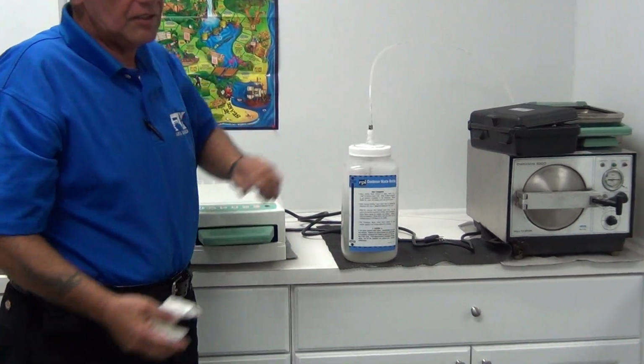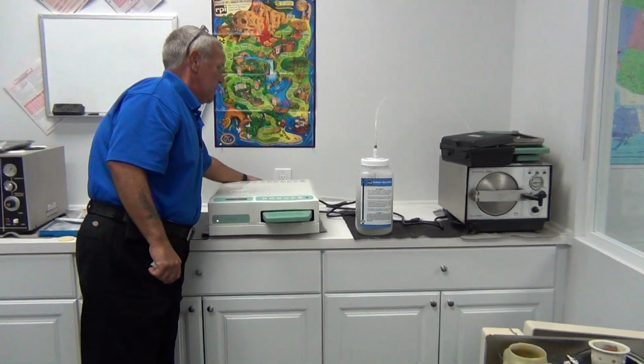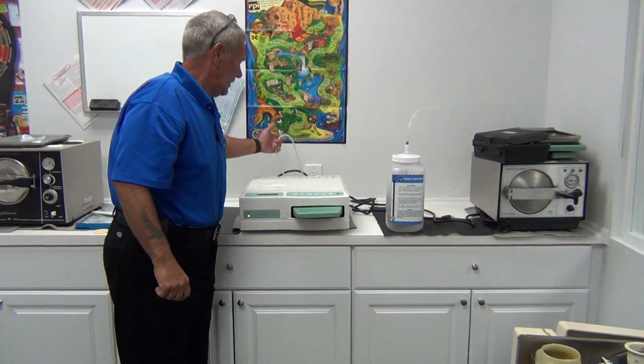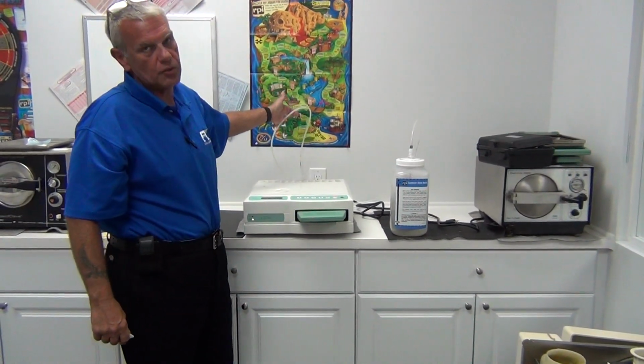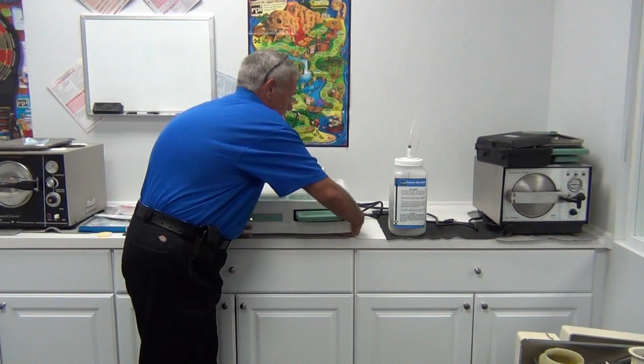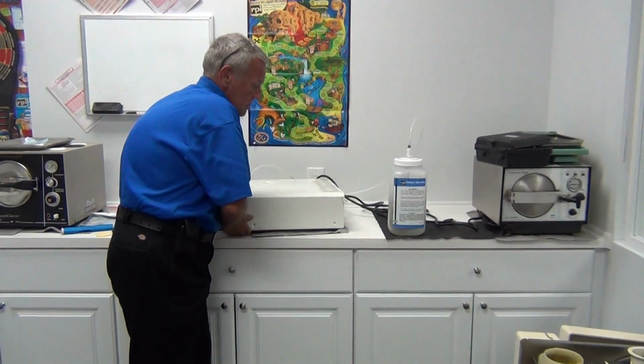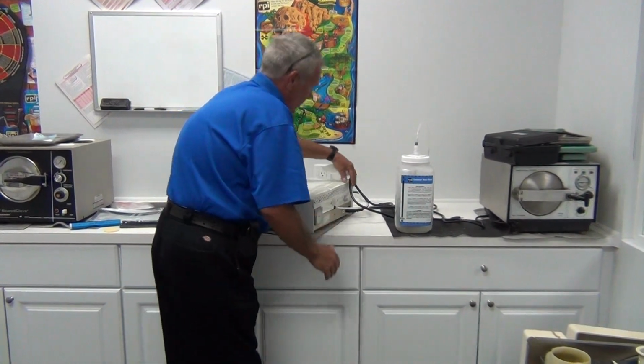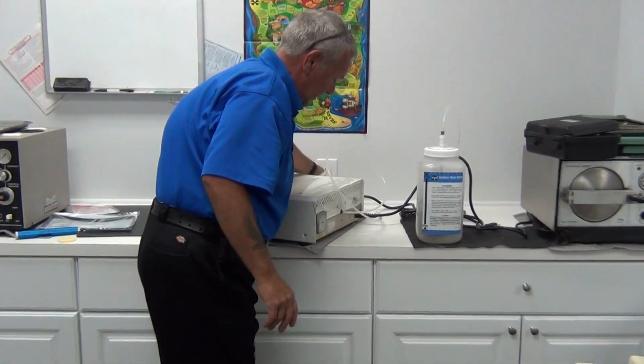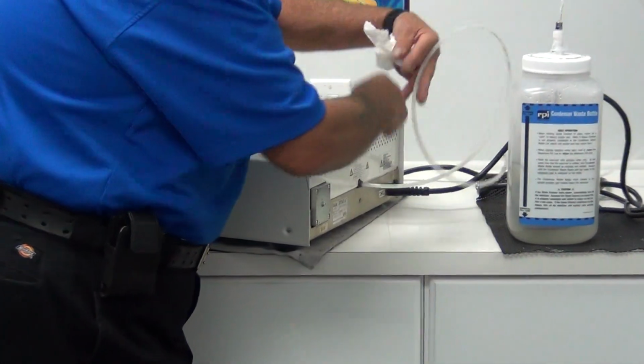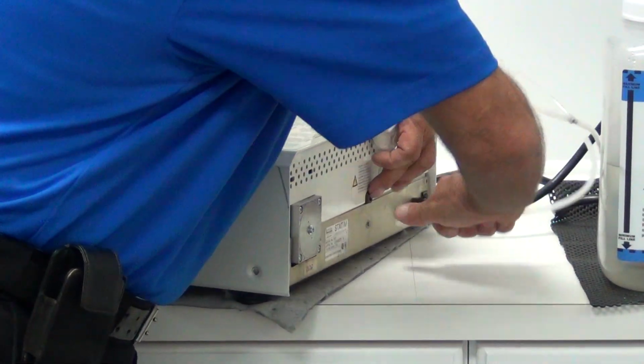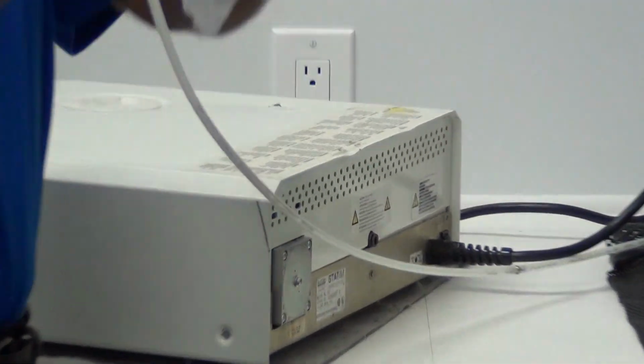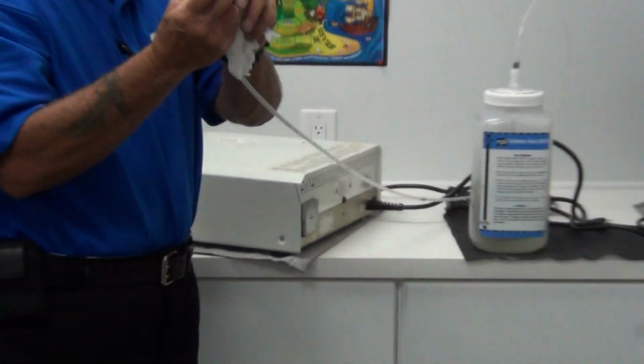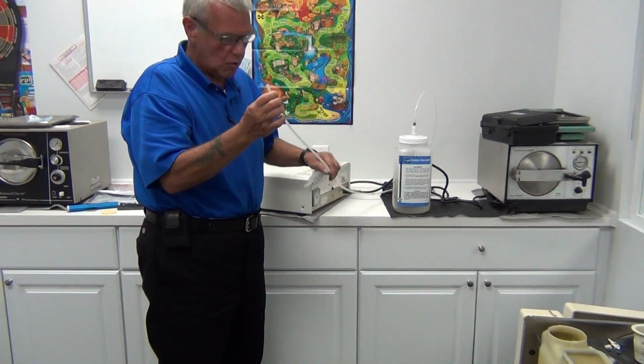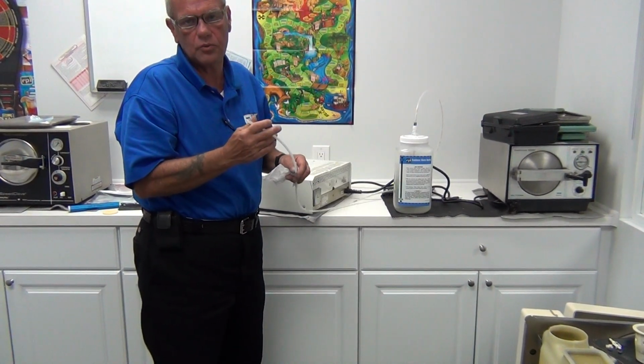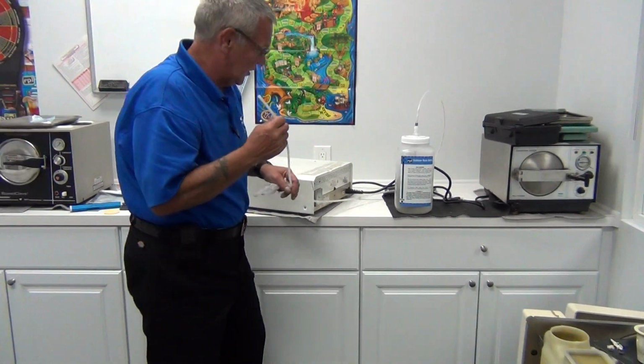Your second level of maintenance that you want to check will be your nylon line that connects the sterilizer to the condenser bottle. You'll want to check, we're going to turn the machine around. You're going to want to check your connections in the back. We'll go ahead and power it now. Check and make sure you have a good solid connection on the back, that the tubing is not worn or frayed, or that there's not any pinholes or creased spots in the tubing. You do not want this tubing to be pinched. Everything depends on this tubing.